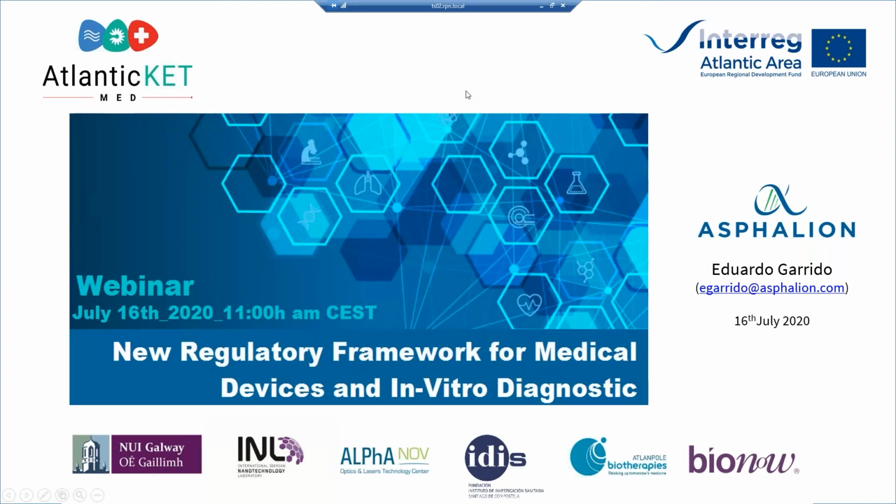Do you have any information about the UK position? Yes, about the UK position. Supposedly, the regulation published by the MHRA, sorry, says CE marked products from Europe are going to be accepted, but it's not going to be the same the other way around. I mean, the notified bodies from the United Kingdom cannot certify products that are going to be marketed in Europe. So you need a notified body based in Europe. It cannot be based in the United Kingdom.